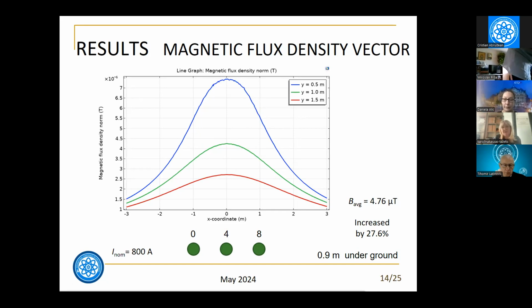When the cables are put a bit higher, at 0.9 meter underground, we have an increase of the average value of the magnetic flux density vector, and the average value is 4.76 microtesla, and as you can see, the increase is 27.6% compared to the previous arrangement.